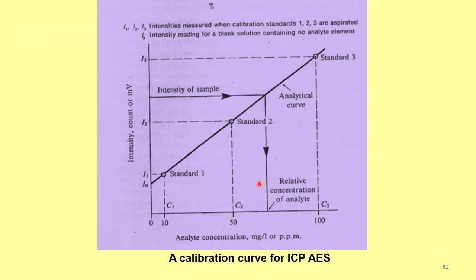I told you it will be linear over several orders. So, right from 0 ppm I can go up to 1000 ppm also. So, I prepare standards from 10 ppm, 20, 50 ppm, 100 ppm, 1000 ppm, still I should be able to get a linear curve, and wherever my unknown sample fits I should be able to determine it. So, that is the beauty of ICP AES.